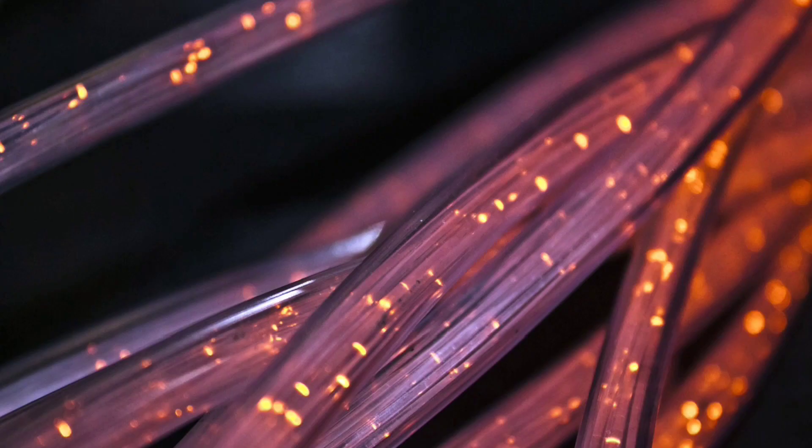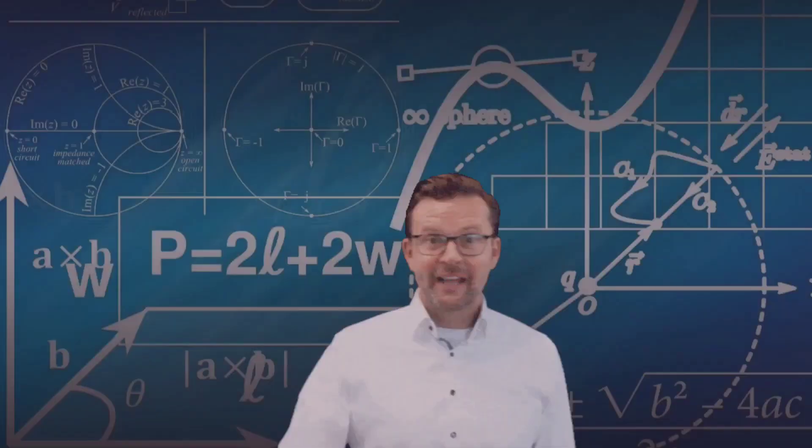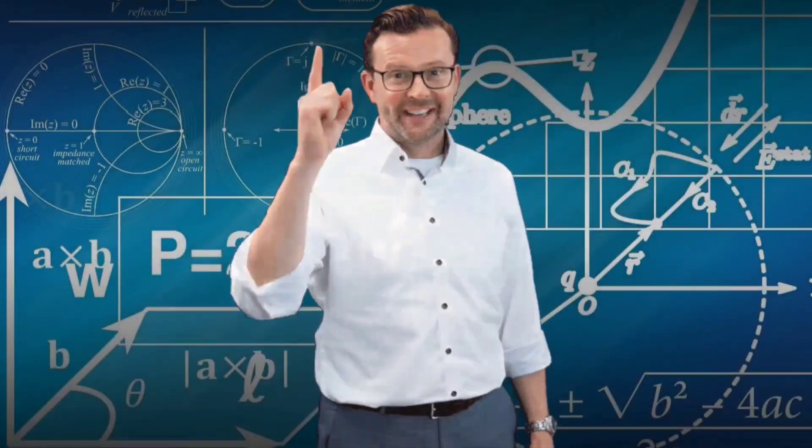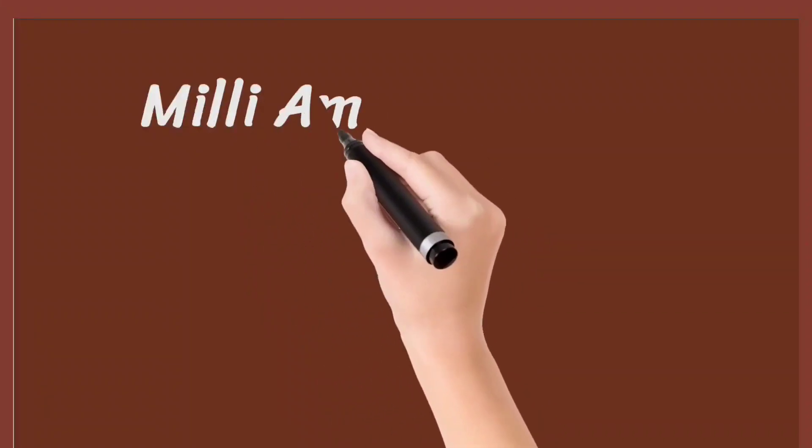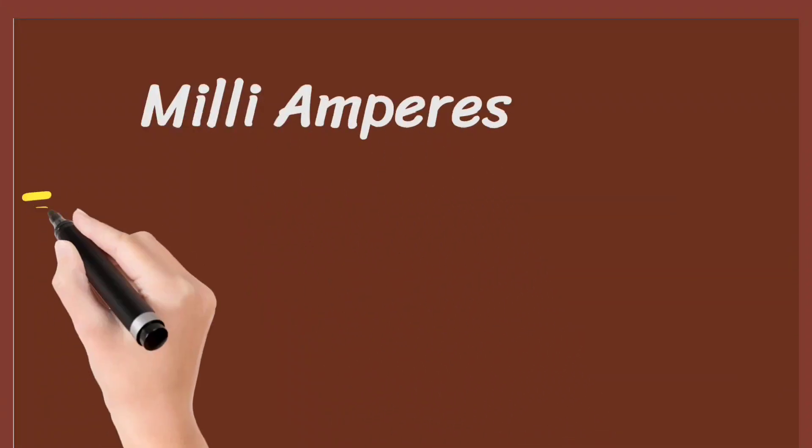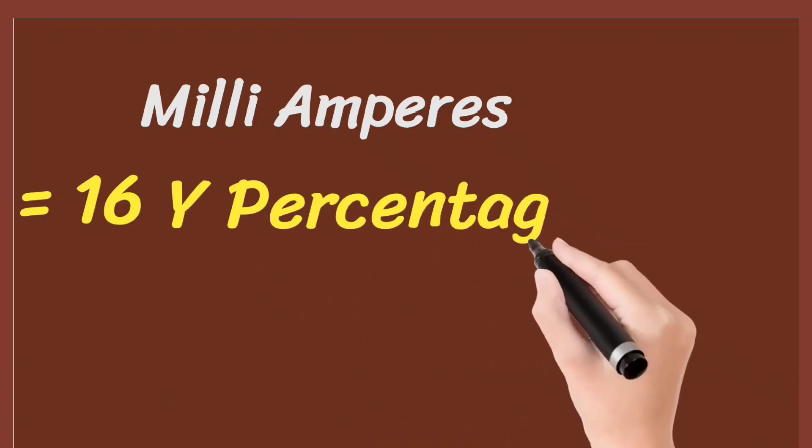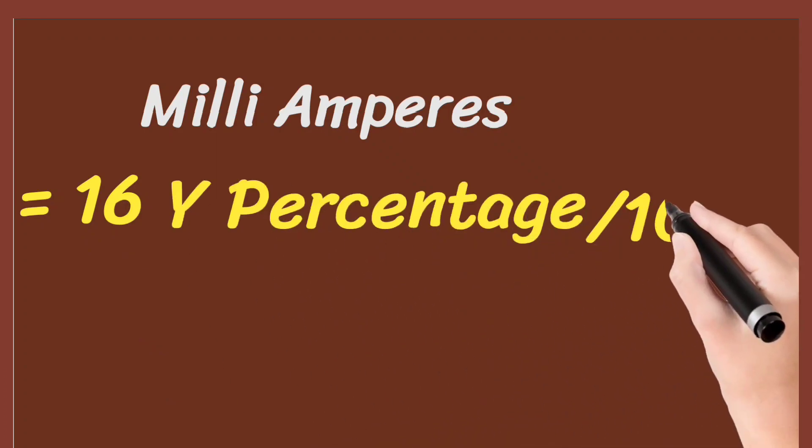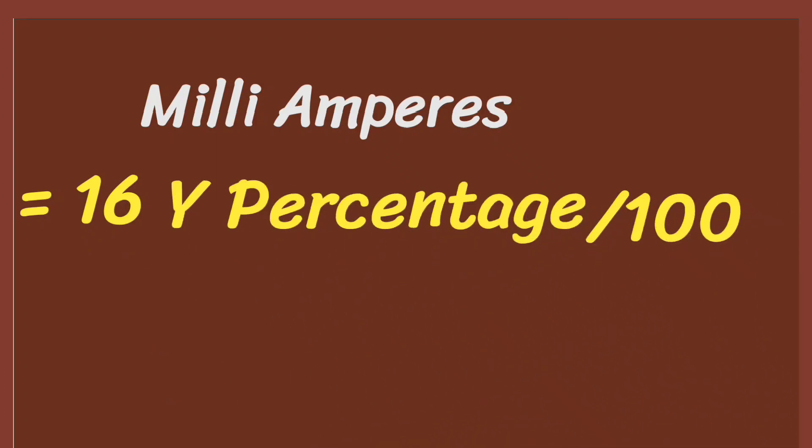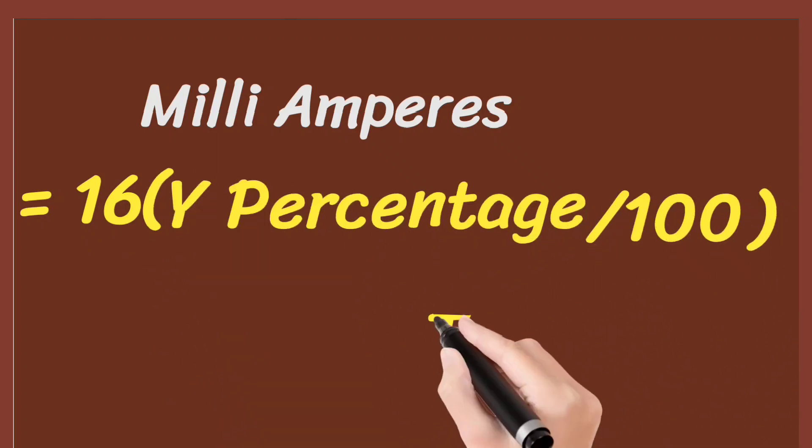Now the formula is: milliamperes equals 16 multiplied by Y divided by 100 plus 4.